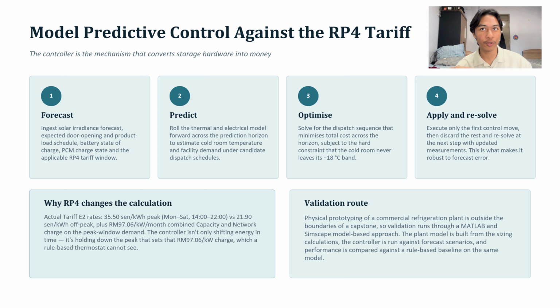Okay, so how does the actual controller decide what to do? MPC against the RP4 tariff. There are 4 steps. First is forecast. It gathers data: the solar irradiance, expected door activity, battery state, PCM state, and the current RP4 tariff. Once it knows that, it can predict from a formulation and calculation what would happen thermally and electrically, so it can predict what room temperature and power it needs. Then it optimizes what we use and what we don't use, so that it stays at negative 18 degrees constantly. And fourth, after it does all that, it throws the plan away and does it again, so that it can always adapt to newer data and be a better model.